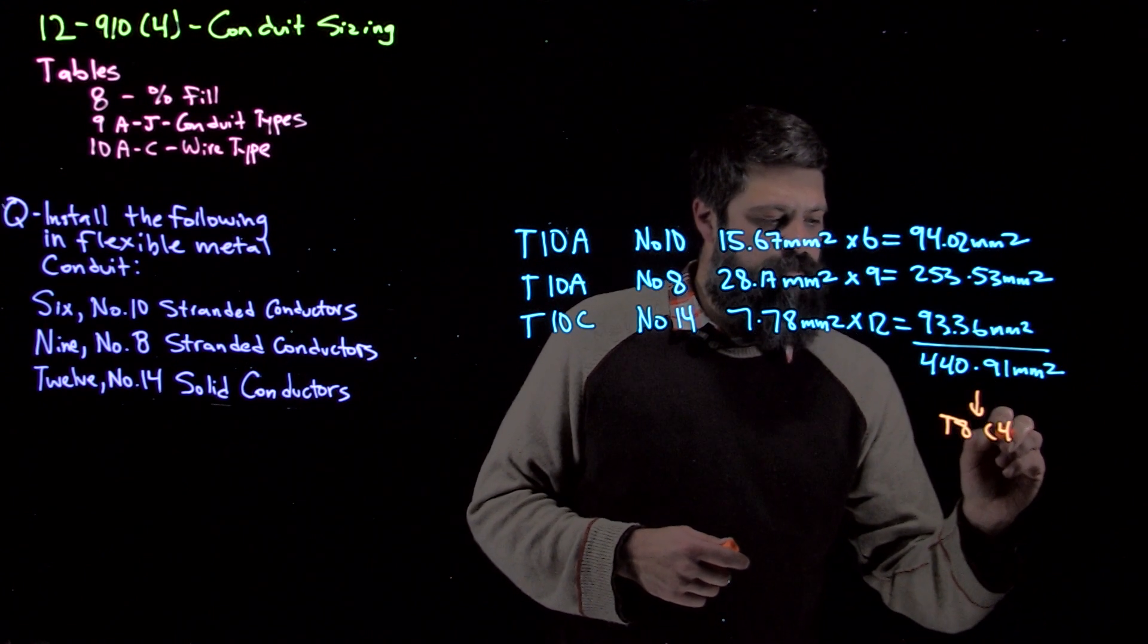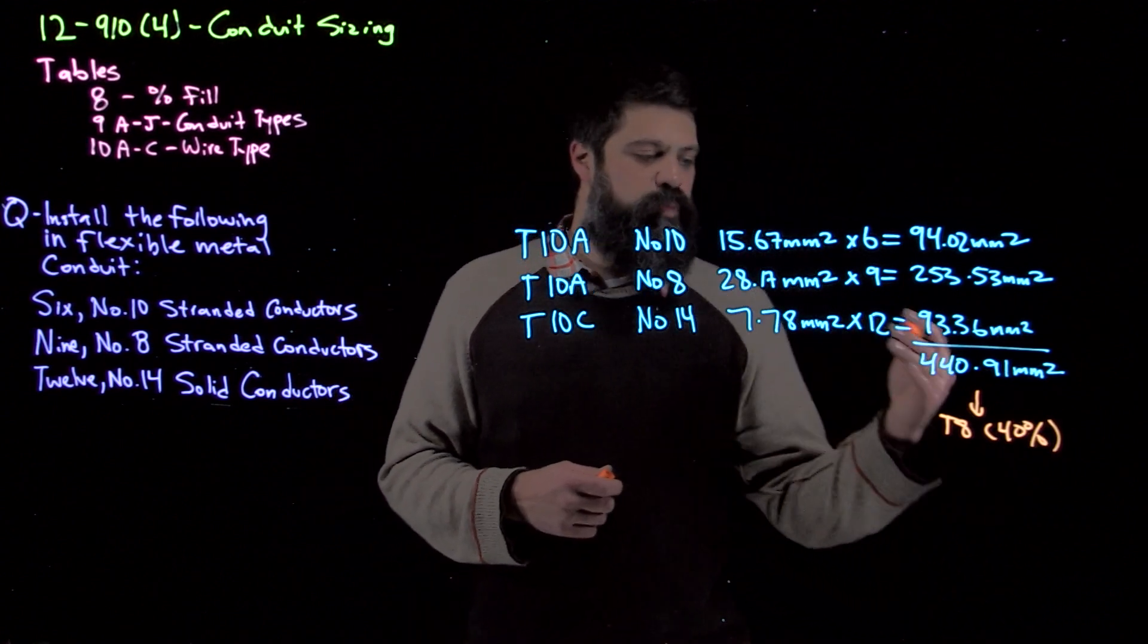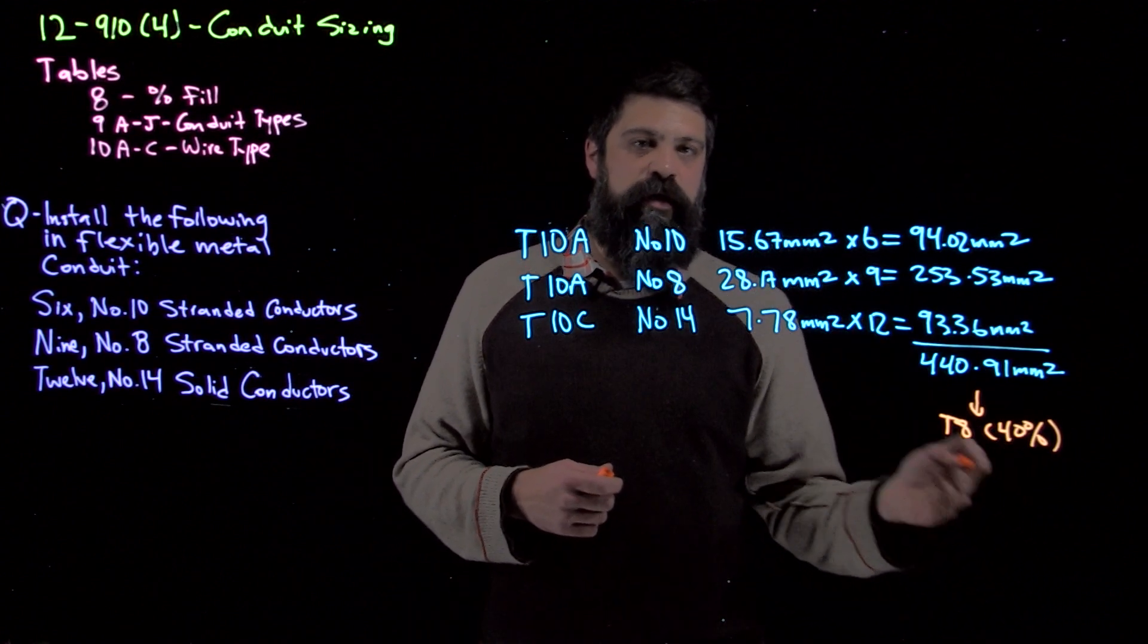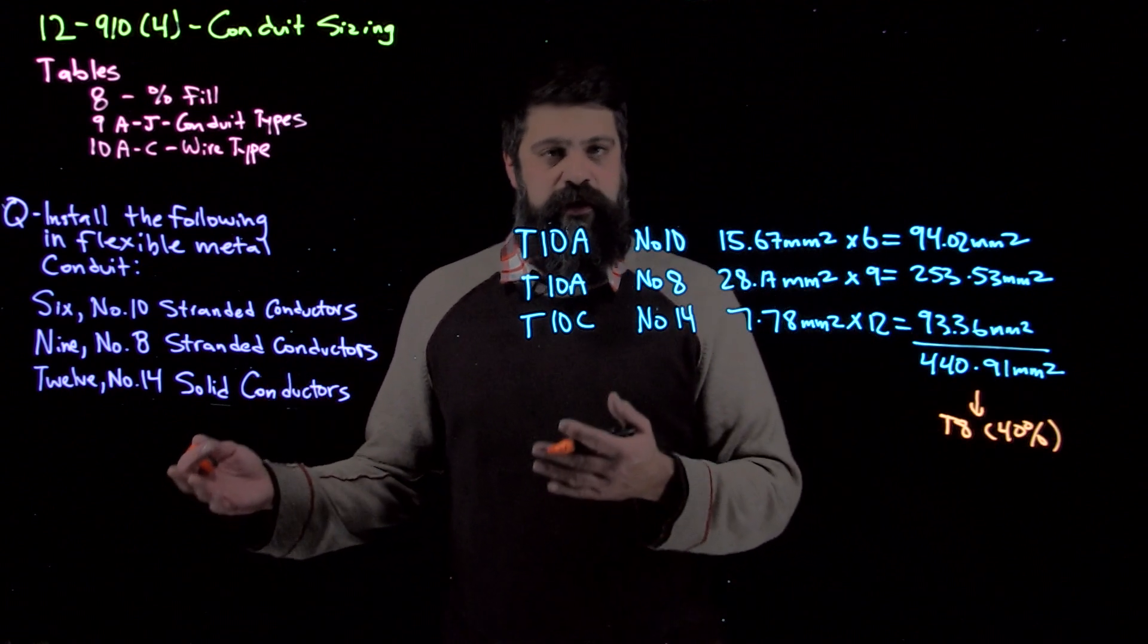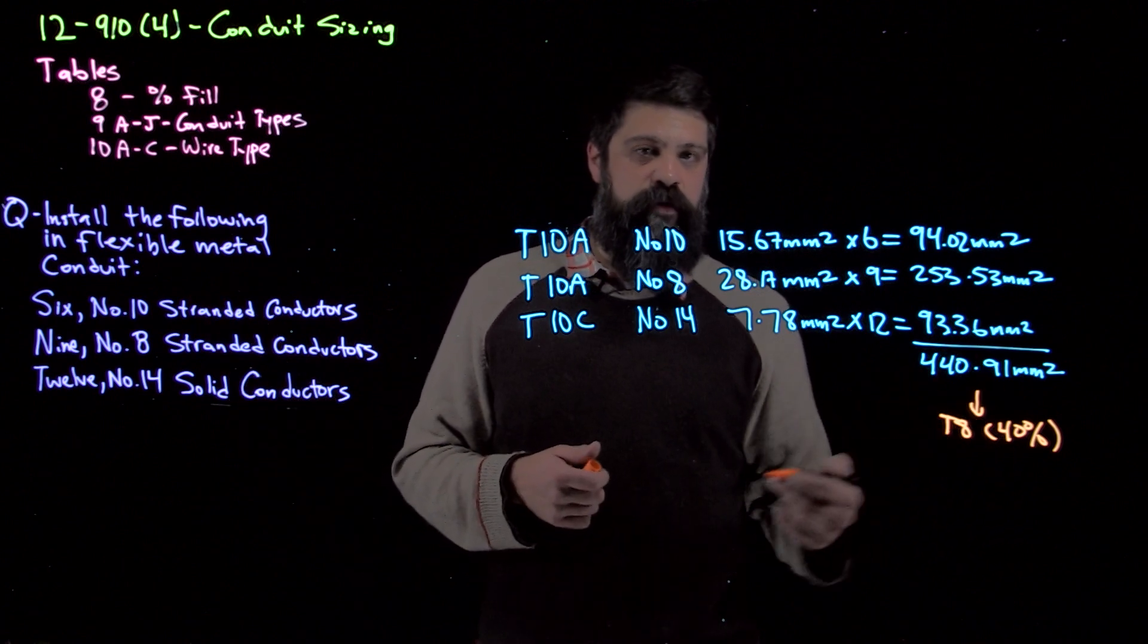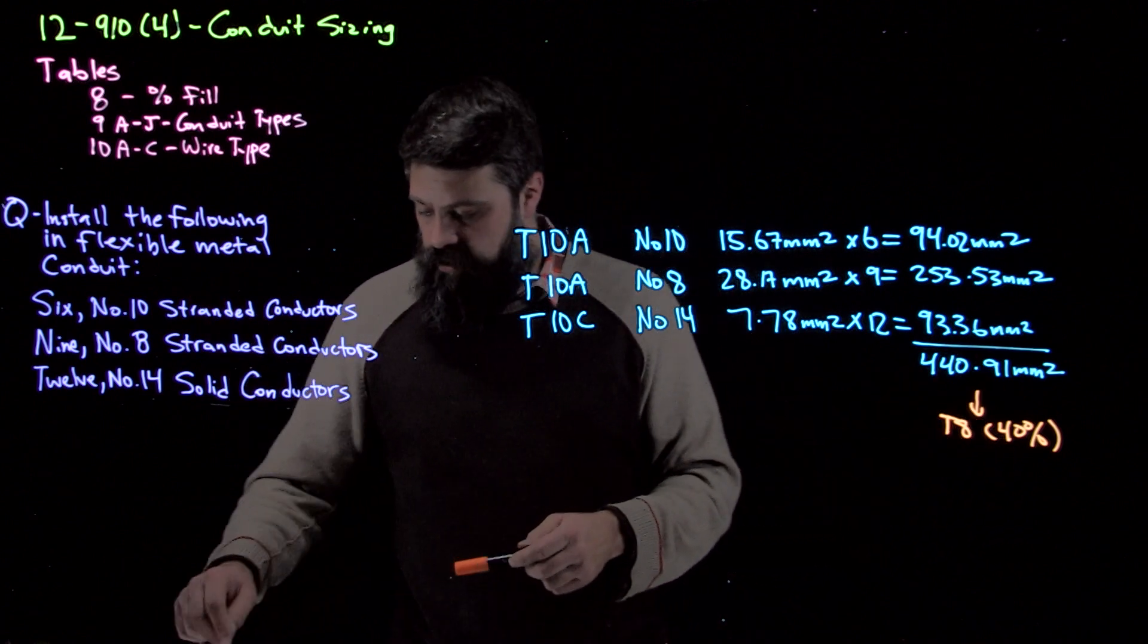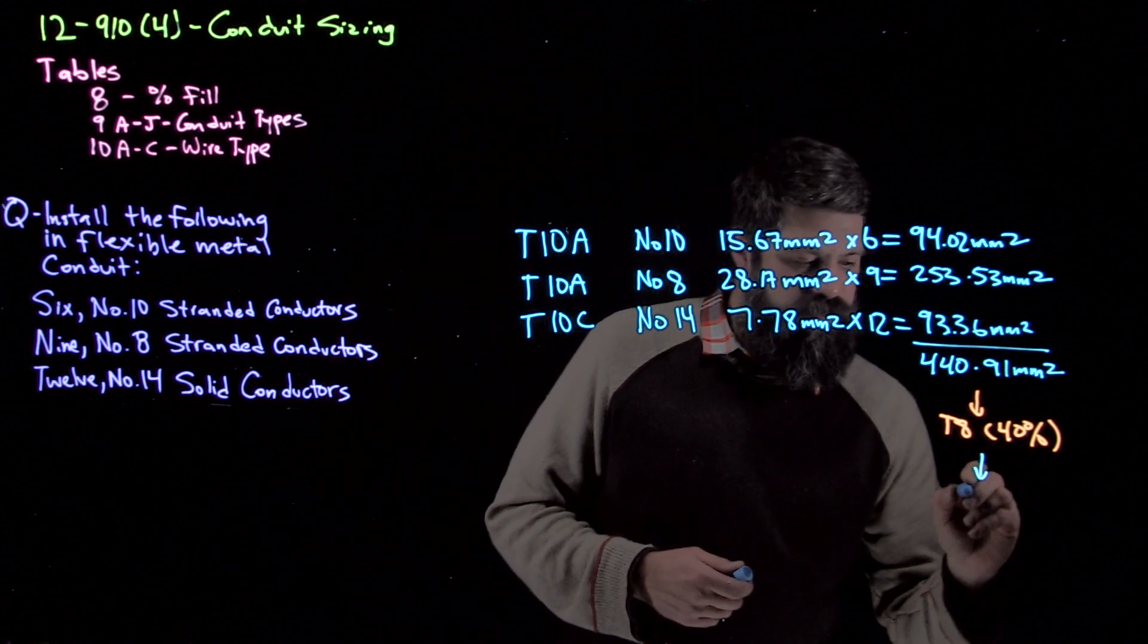Table 8 tells me 40%. The only reason we need that now is because when we go through tables 9A to J, we have all our columns that give me a percentage fill that I'm allowed. So once I find the conduit that I'm looking for from tables 9A through J, I'm going to be looking in the 40% column. For us, we're going to put this in flexible metal conduit. So that's going to take us to table 9B.